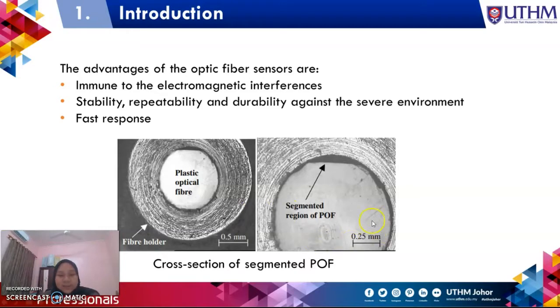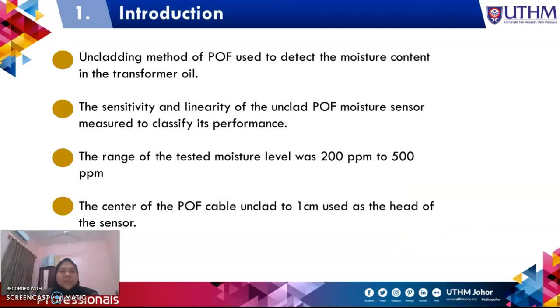So this is the cross section of the segmented POF. In this research, we're going to use the uncladding method of the POF to detect the moisture content in the transformer oil. The sensitivity and linearity of the unclad POF moisture sensor are going to be measured to classify the performance of the POF sensor. The range of moisture level used to test in this research is 200 ppm to 500 ppm. The center of the POF cable is unclad to 1 cm, which is used as the head of the sensor.